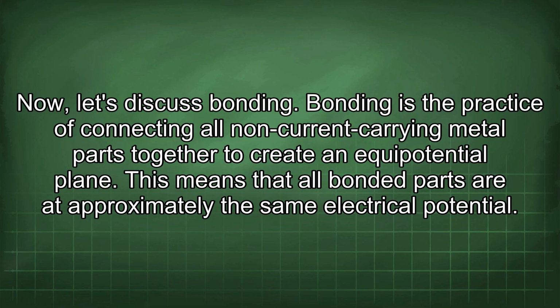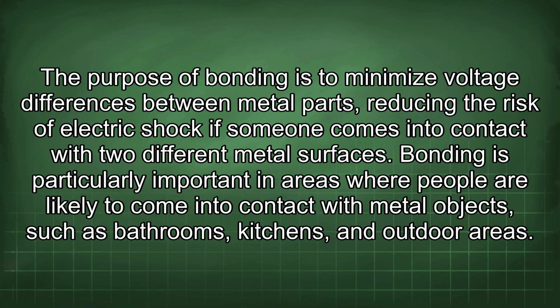Bonding is the practice of connecting all non-current carrying metal parts together to create an equipotential plane. This means that all bonded parts are at approximately the same electrical potential. The purpose of bonding is to minimize voltage differences between metal parts, reducing the risk of electric shock if someone comes into contact with two different metal surfaces.